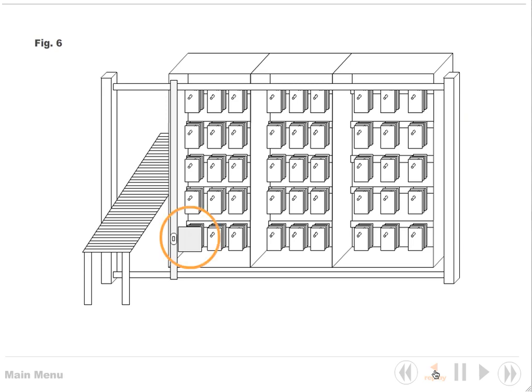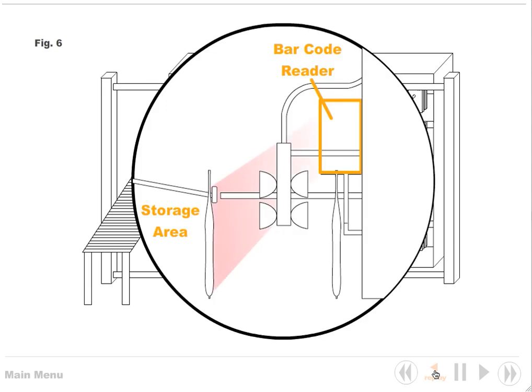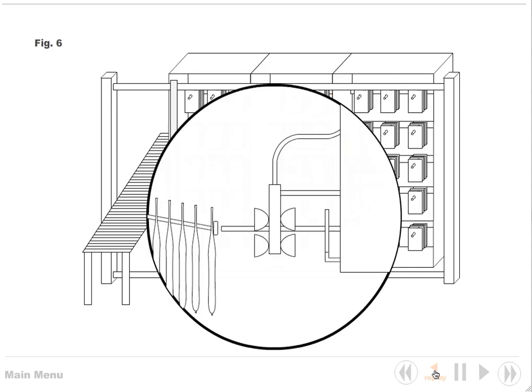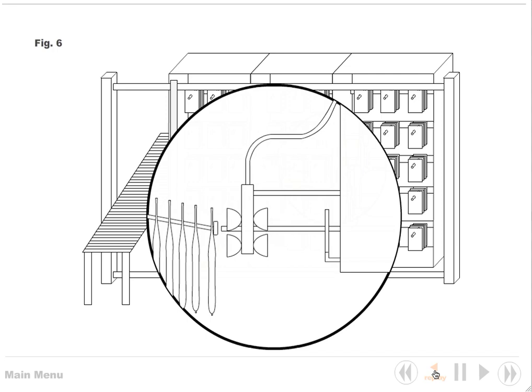Once the picking means is in a location opposite the aspirin, the picking means removes the package from the storage rod. If the picking means includes a package reader, the reader first scans the aspirin package on the storage rod to confirm it is the correct medication before removing it from the storage rod. Picking occurs through forward movement of the suction head. As the suction head moves forward, it contacts the package of aspirin to be picked.